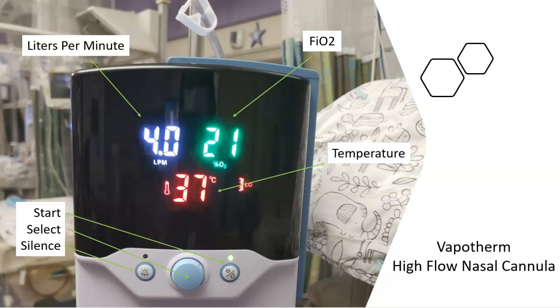FiO2 21 to 100%, and then temperature 34 to 37 degrees. If you want to make a change, this is your select button. You can select until you are on where you want to change. So let's say you can select until one of these is flashing, and then turn the knob. This will turn left and right to where you want it set, and then it will automatically set. You can either leave it and it will set it, or else you can just press the select button again and it will confirm that setting change.